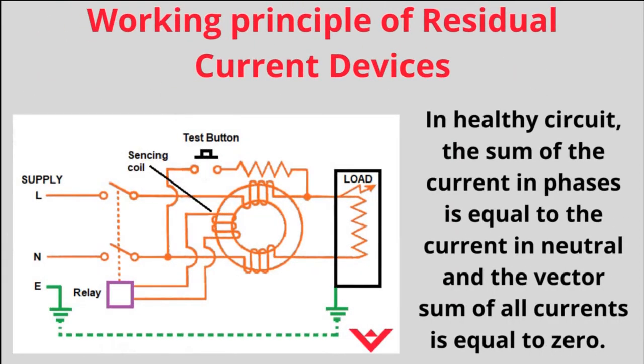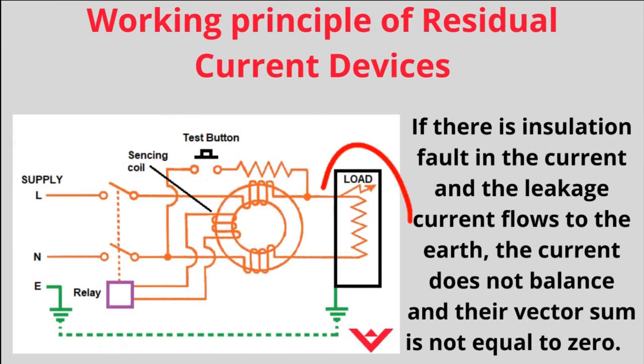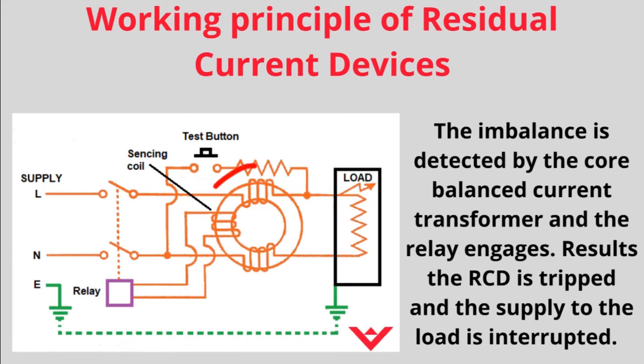In a healthy circuit, the sum of the currents in the phases is equal to the current in the neutral, and the vector sum of all currents is equal to 0. If there is an insulation fault in the circuit and leakage current flows to earth, the current does not balance and the vector sum is not equal to 0. The imbalance is detected by the core balanced current transformer and the relay engages. As a result, the RCD is tripped and the supply to the load is interrupted.